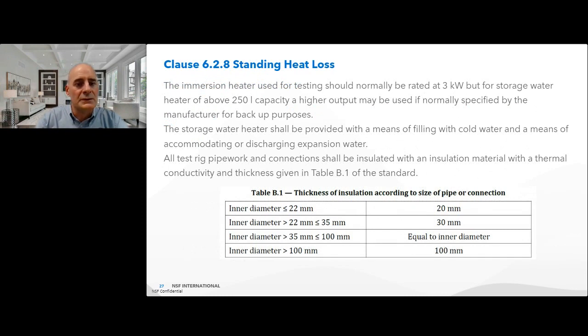The immersion heater used for testing should normally be rated at 3 kilowatts, but for storage water heaters of above 250 litres capacity, a higher output may be used if normally specified by the manufacturer for backup purposes. The storage water heater should be provided with a means of filling with cold water and a means of accommodating or discharging expansion water. All test rig pipework and connections should be insulated with an insulation material with a thermal conductivity and thickness given in Table B1 of the standard, and as shown below.